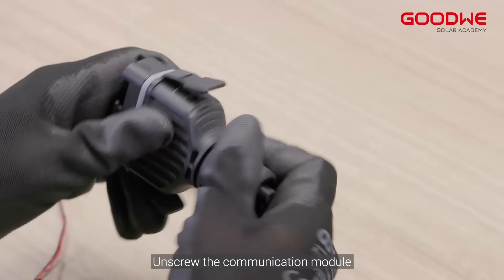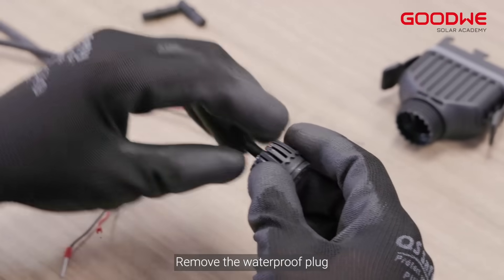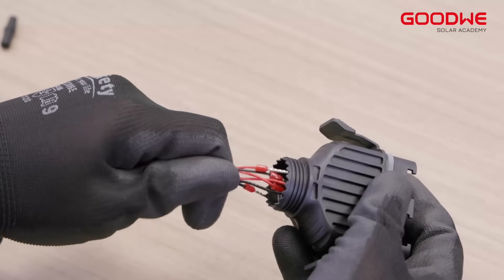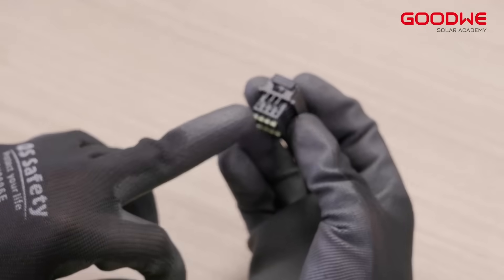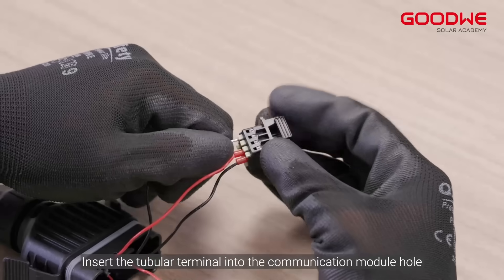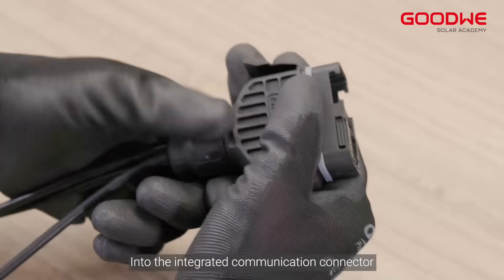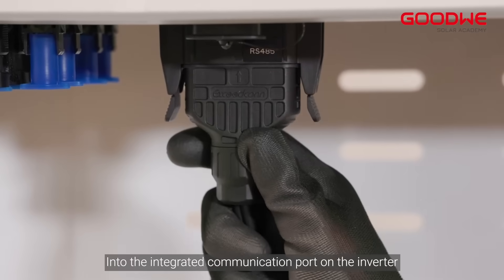Unscrew the communication module, then remove the waterproof plug. Route the communication cable into the integrated communication connector in sequence. Insert the tubular terminal into the communication module hole, and connect the communication module into the integrated communication connector. Insert the integrated communication connector into the integrated communication port on the inverter.